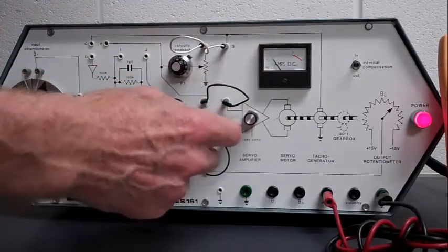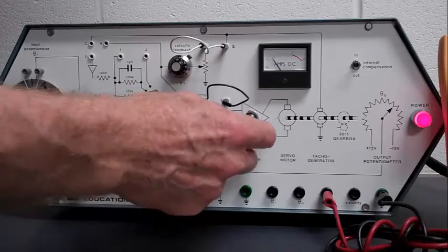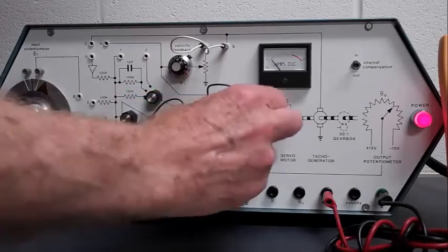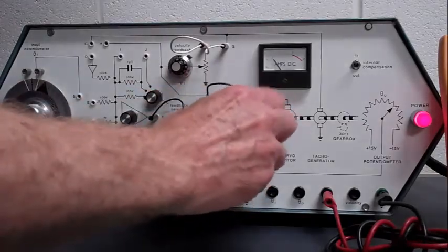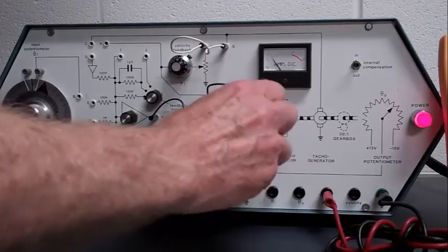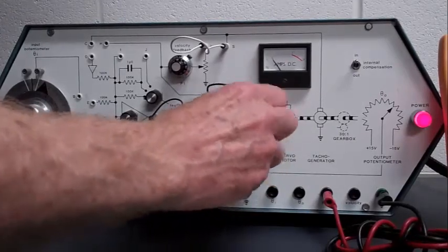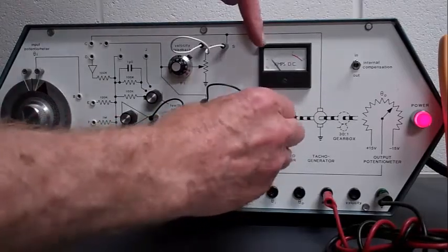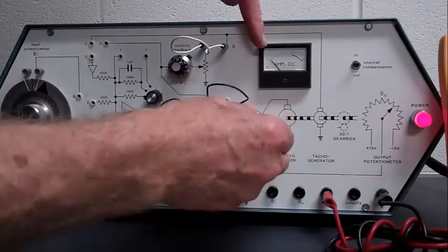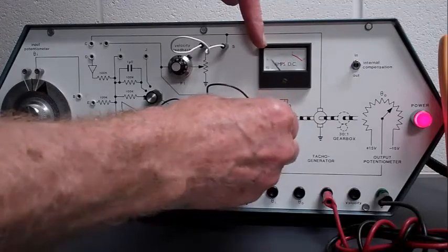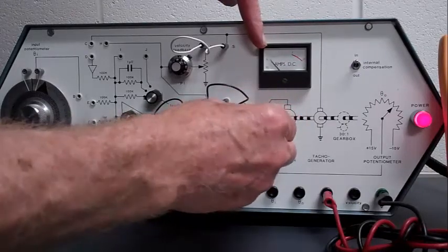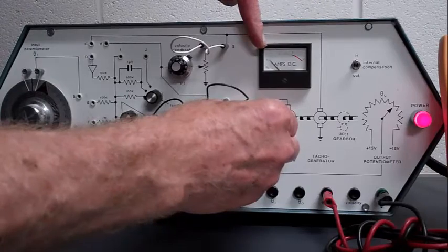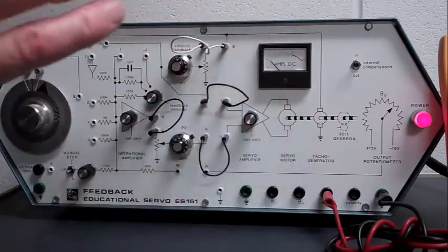Now after sitting for several months, there's an oxide layer built up. So we just turn it back and forth rapidly. We can scrape off some of that oxide layer and then we watch the needle and make it dip as low as possible. That's pretty good right there.